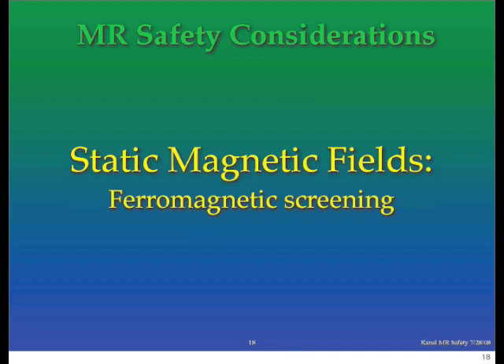There is a new kind of metal detector, the last five or so years, called a ferromagnetic detector. Ferromagnetic detectors detect only metals that find themselves attracted to magnetic fields. That's an entirely different story. I, as well as the ACR's Safety Committee, as well as the Joint Commission — that is something I think is appropriate for us to be aware of. I use them and suggest that others use them in their screening.